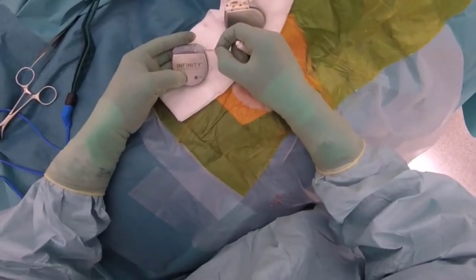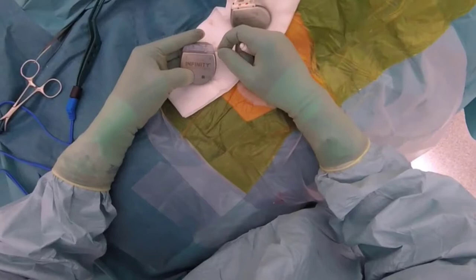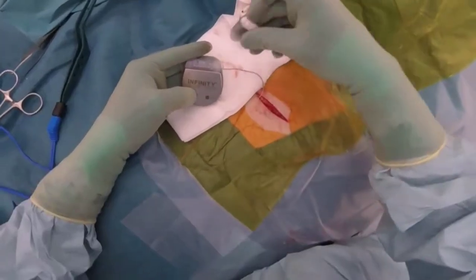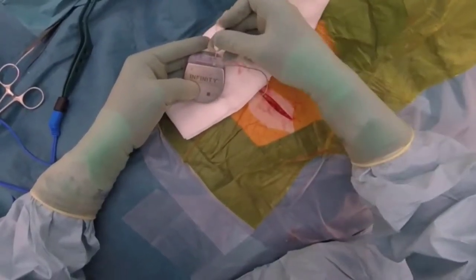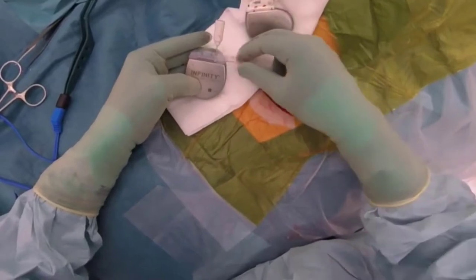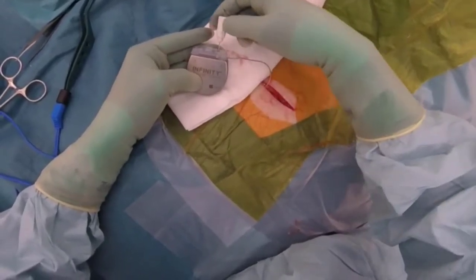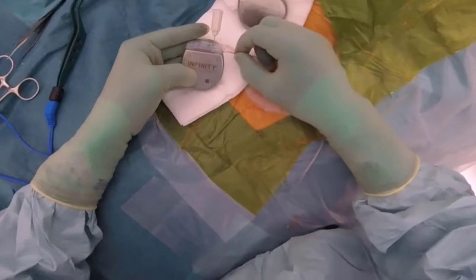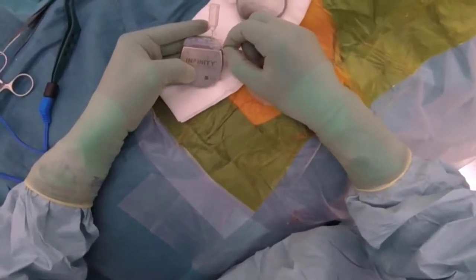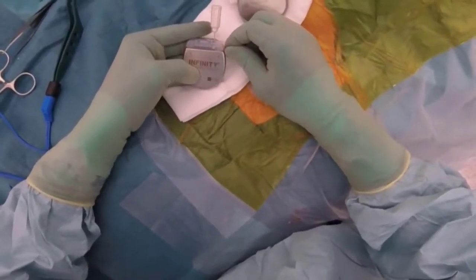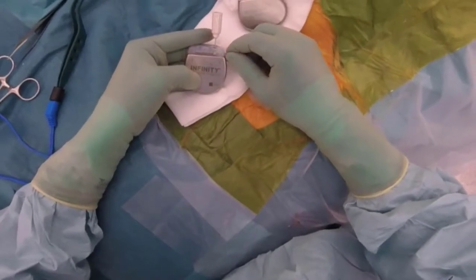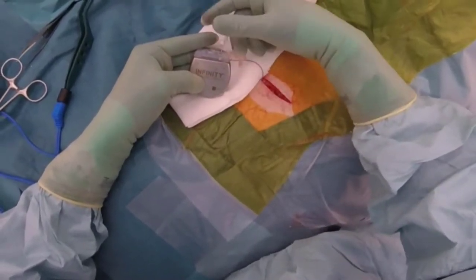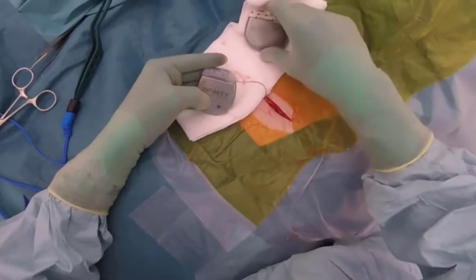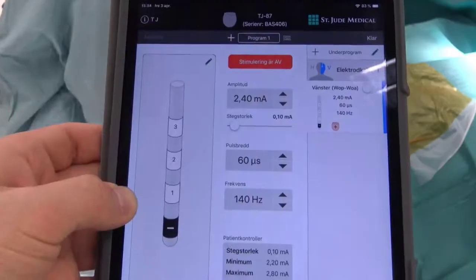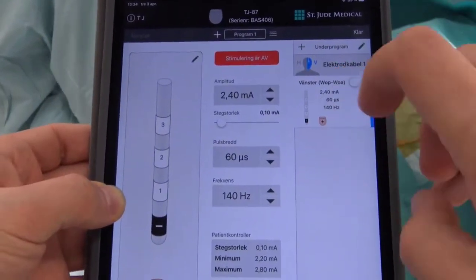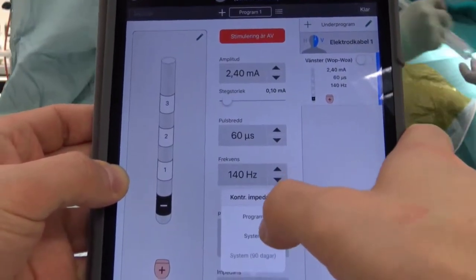The cable is then inserted into the new IPG. Make sure that the lock screw is opened, and you can then insert the cable to the bottom of the socket. We then lock the screw, and verify that the impedance is okay.